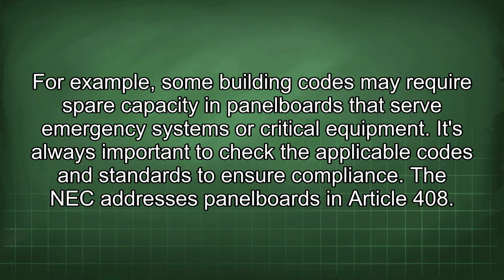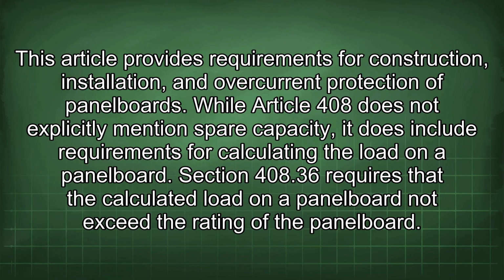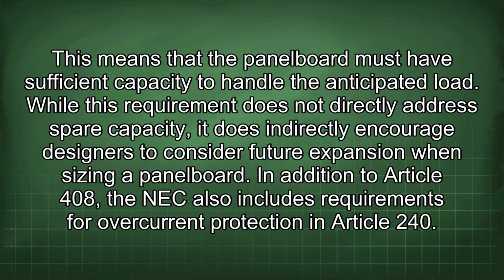The NEC addresses panel boards in Article 408. This article provides requirements for construction, installation, and overcurrent protection of panel boards. While Article 408 does not explicitly mention spare capacity, it does include requirements for calculating the load on a panel board. Section 408.36 requires that the calculated load on a panel board not exceed the rating of the panel board. This means that the panel board must have sufficient capacity to handle the anticipated load. While this requirement does not directly address spare capacity, it does indirectly encourage designers to consider future expansion when sizing a panel board.